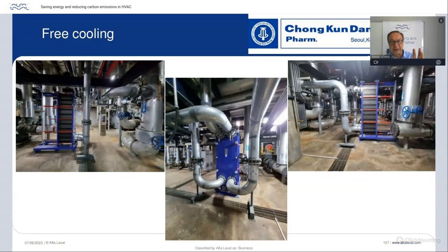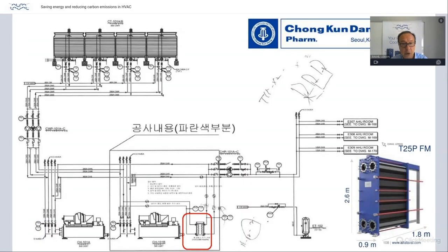This is a quick look at the heat exchanger. It's the same heat exchanger with three different views. So this is an Alfa Laval plate heat exchanger working between the cooling tower and the water going to the air handling units. And this is a HVAC application in the pharmaceutical company it is. So what we have here is 1, 2, 3, 4 cooling towers, which are providing cold water down to 2 chillers. One is here, the other is here. And what our Energy Hunter partner in Korea has done is installed an Alfa Laval plate heat exchanger here. And there is no automation. It is, again, very, very manual. And what they do is they divert the cooling tower water at 6 degrees Celsius, going to the plate heat exchanger and then returning to the tower.